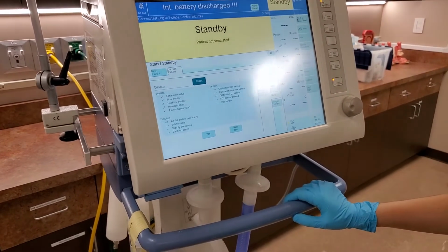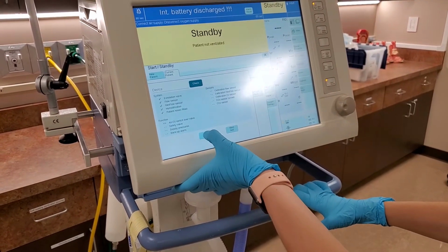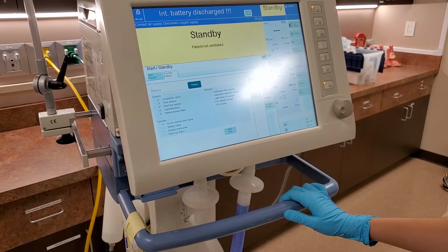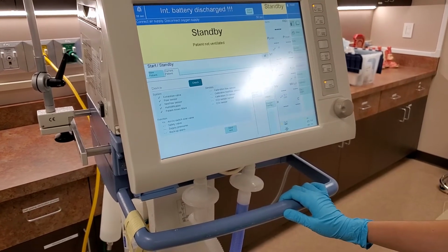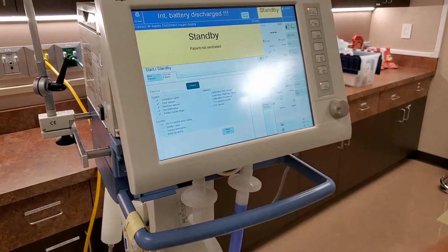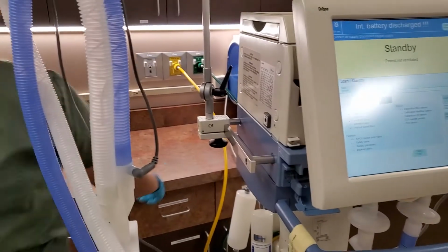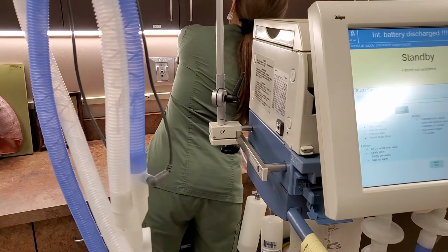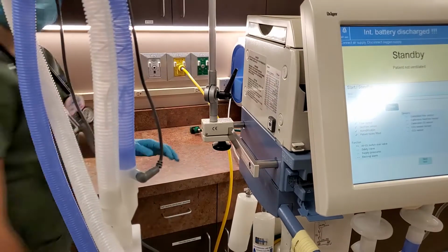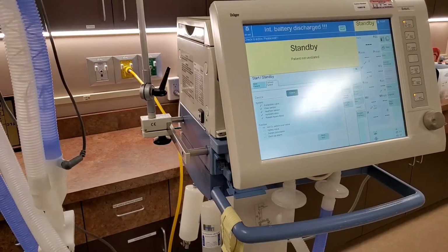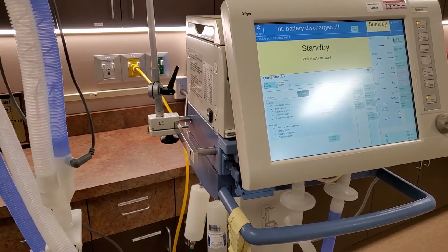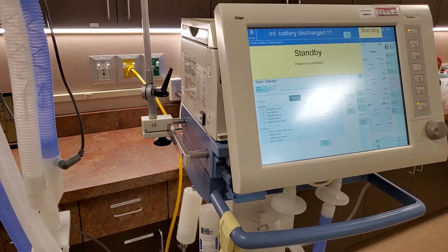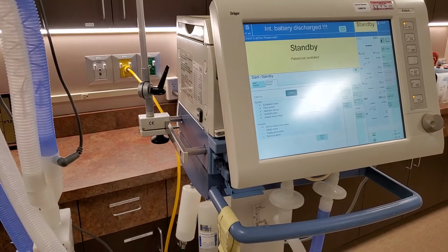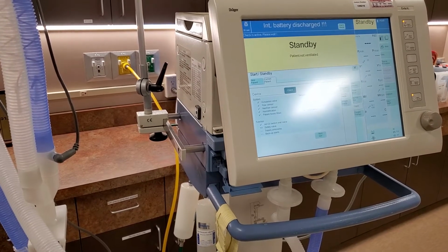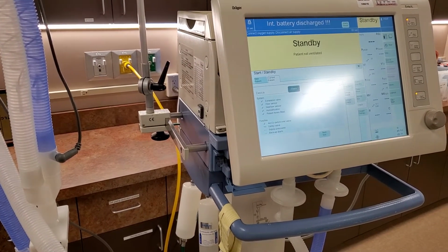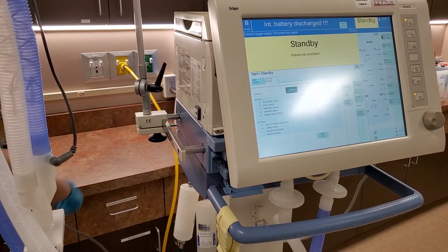And then connect the test line to the white piece again. Confirm with yes. Connect oxygen supply, and then it says connect air supply, disconnect oxygen supply. So you come down to here and you would disconnect your oxygen. Now it recognized that. It's checking again. It's saying connect the oxygen and disconnect the air.